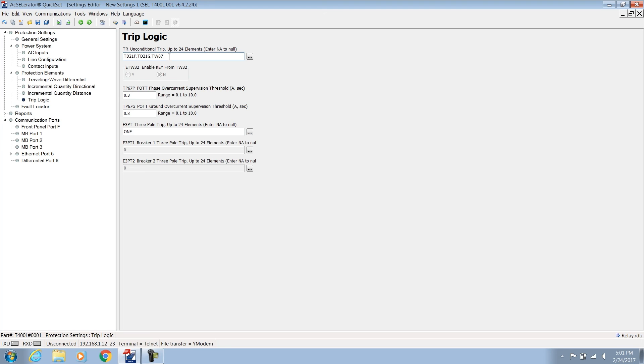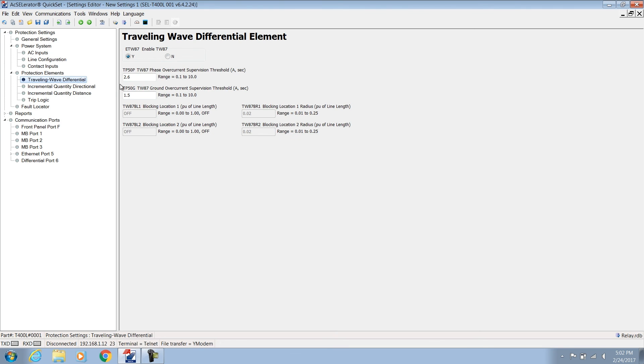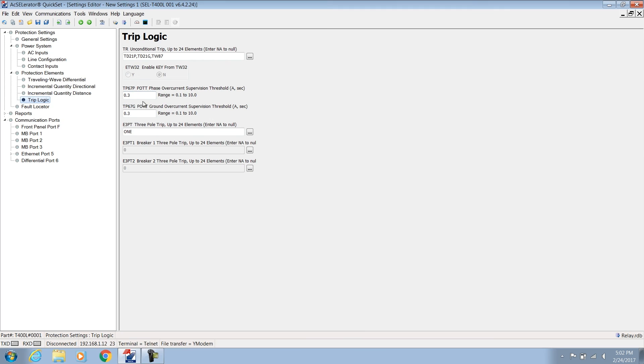The POTT scheme is inherently very sensitive. Two overcurrent settings are provided to limit the sensitivity to the level required by the application. In non-series compensated lines, these two thresholds are set similarly to the counterpart settings in the TW87. We use 2.6 and 1.5 amps secondary respectively for the phase and ground elements. Let's use the same values to supervise the POTT operation.